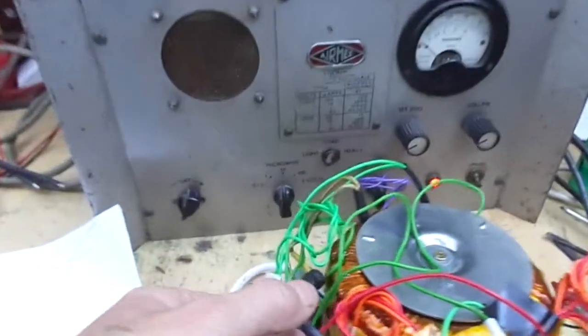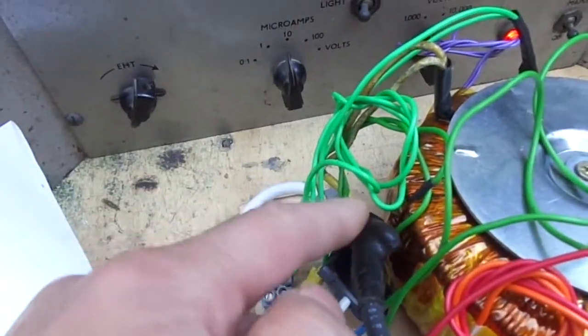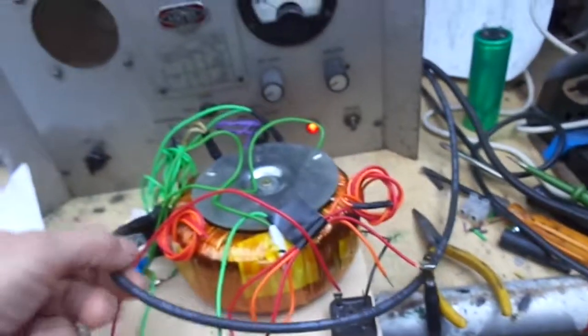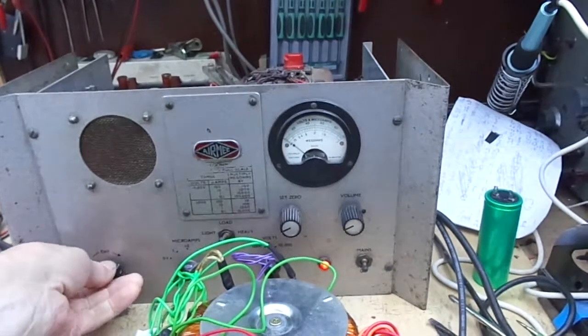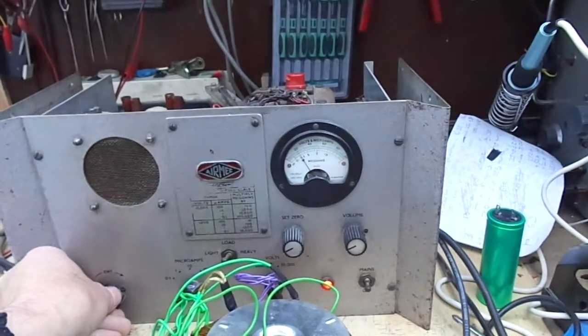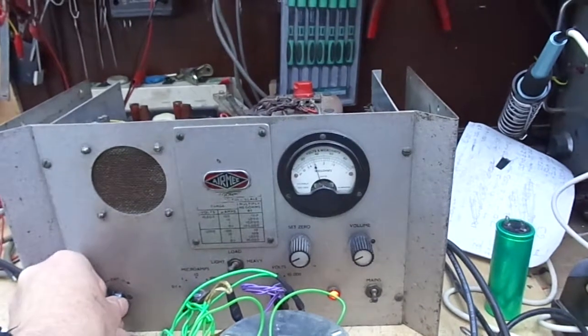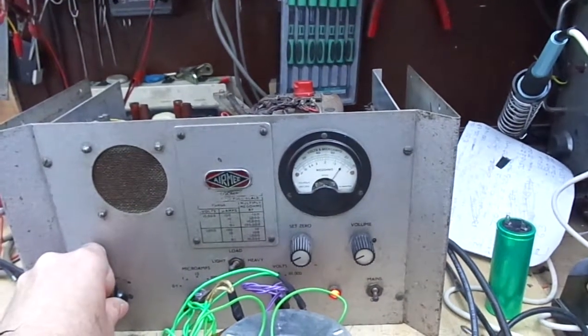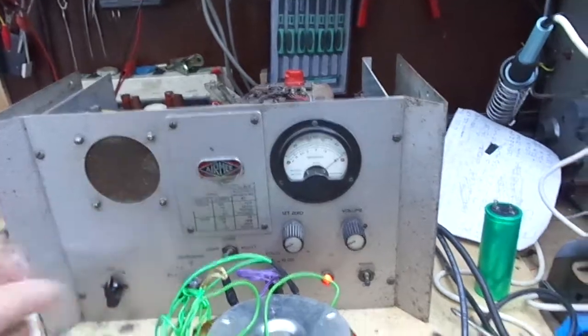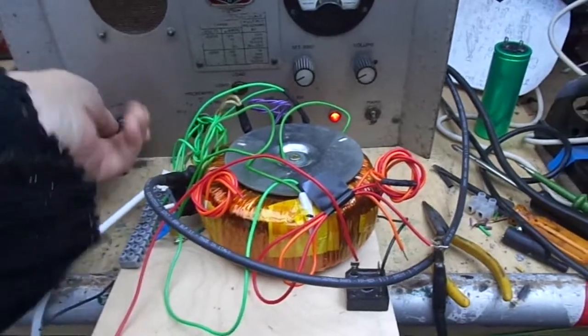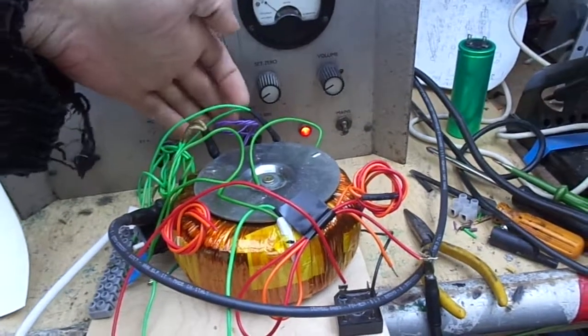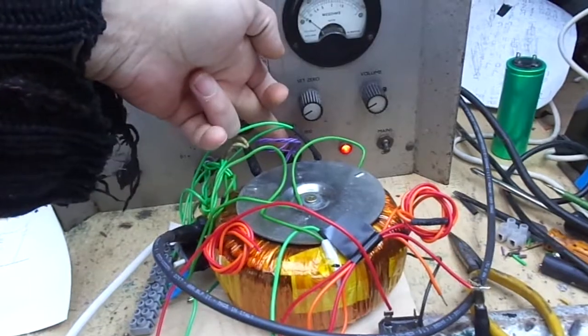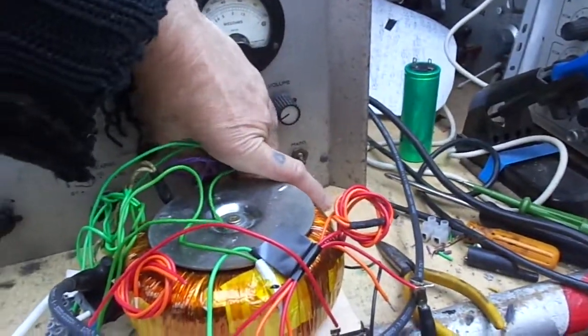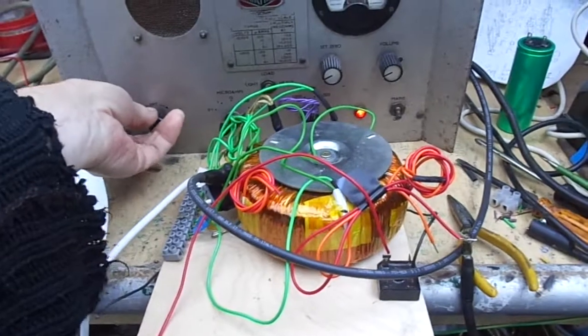So I've got one side connected to the primary, that's the earth, and then this is our high voltage lead. Put it on the right setting, 200 volts, got it on the wrong setting there, 400 volts, 800 volts, 1000 volts between the primary and the secondary. Click that off, bring it on to, if I can just get in there, put it on the 10,000 volt setting.